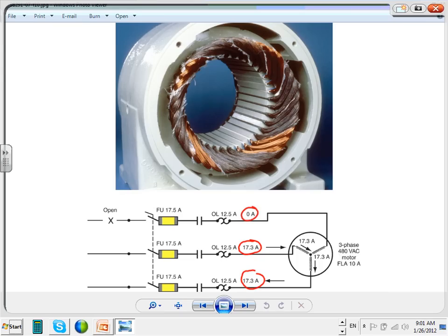Okay, 17.3. Now, if this overload is sized properly, 12.5, do you think it's going to take care of this problem and help you? Yeah, it will open. So overload will protect you from single phasing too, not just from overloading the motor. This is called single phasing, when you have a motor open.